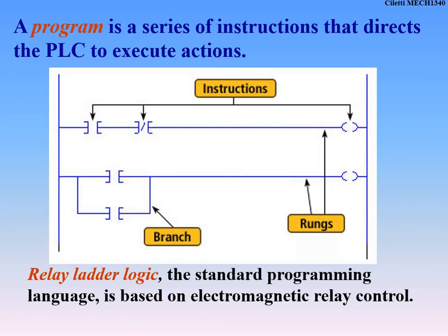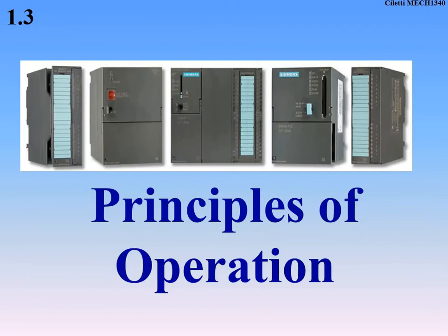A branch is technically an OR operation. This relates back to those of you who took digital electronics — ANDs, ORs, inverters, NAND, NOR, and exclusive ORs all come back into play. All of that translates into ladder logic. If I look at the top rung, those two contacts are ANDed together — a normally open and a normally closed contactor. For something to happen, this AND this has to happen. The branch shows two normally open contactors that are ORed together — this OR this can turn the output on.